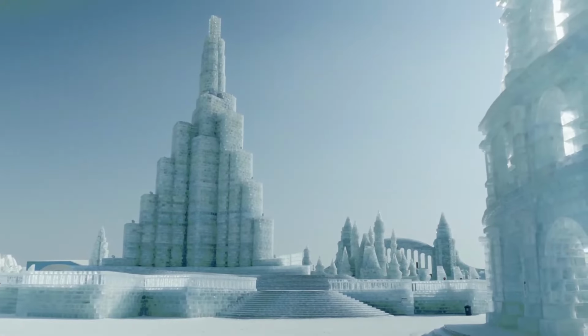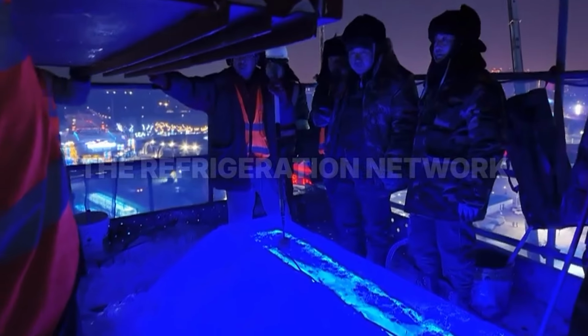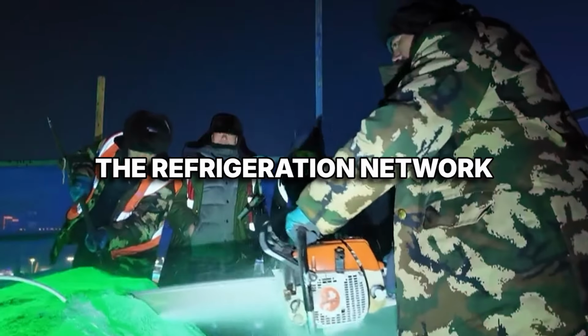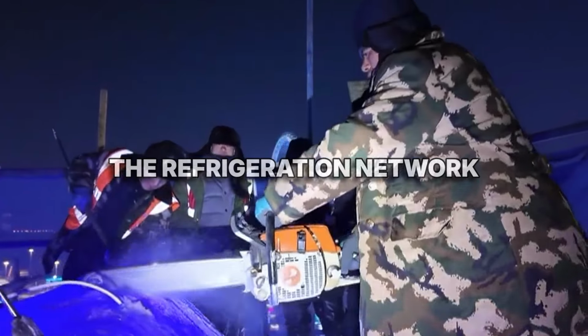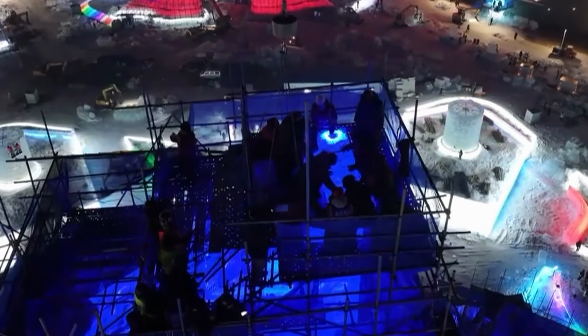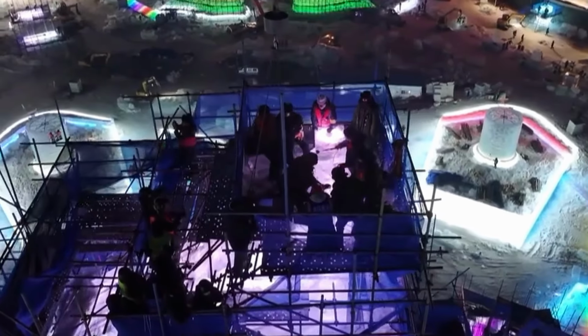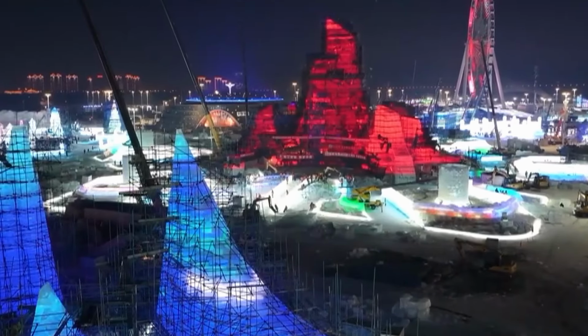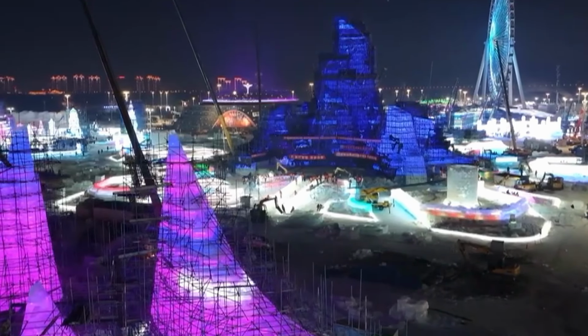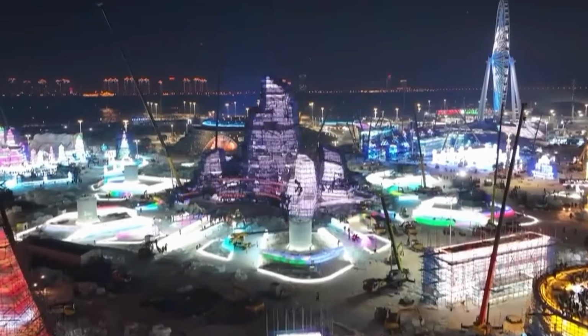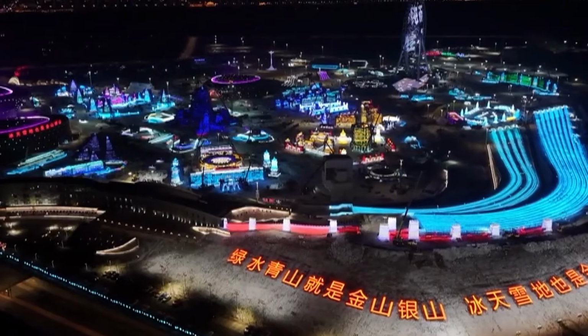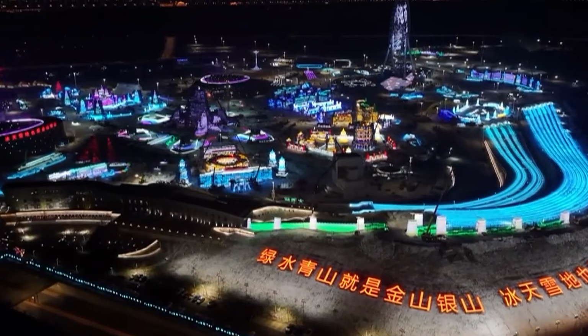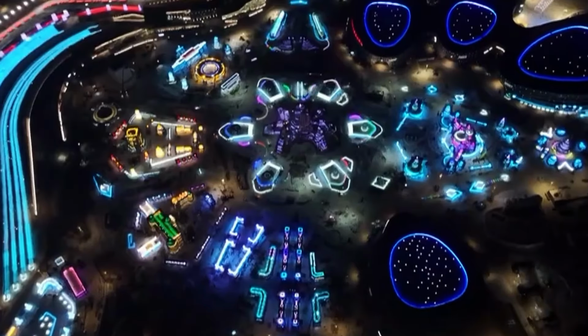But there's something even more critical they're installing right now. The refrigeration network. Underground pipes snake through the entire construction site, pumping glycol coolant at minus 50 degrees Fahrenheit through a network spanning 12 miles. You're looking at an industrial refrigeration system powerful enough to cool 30,000 homes, redirected to keep ice structures frozen in temperatures that naturally want to melt them. Engineers buried these pipes 6 inches below the surface before construction even started, creating a frozen foundation that maintains constant temperature regardless of what's happening in the air above.